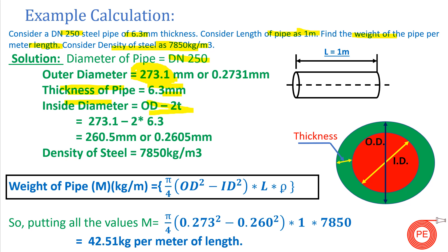Thickness of the pipe is 6.3 mm. To calculate inside diameter: ID = OD − 2t = 273.1 − 2(6.3) = 260.5 mm, which is 0.2605 m. Converting OD to meters: 0.2731 m. Putting all values into the formula: (π/4) × (0.273² − 0.260²) × 1 × 7850, the result is approximately 42.51 kg per meter of length.